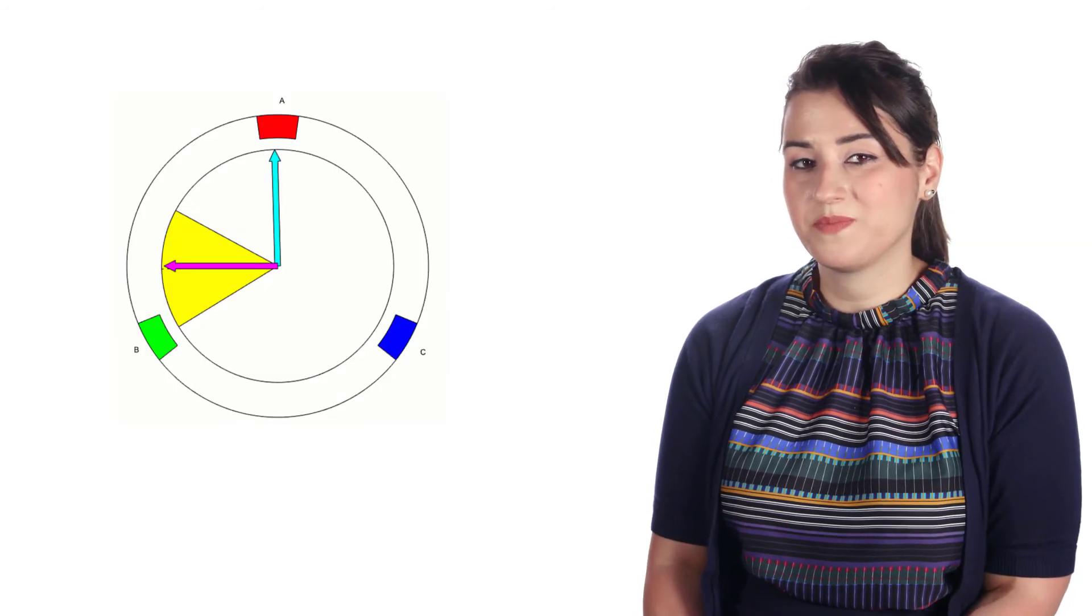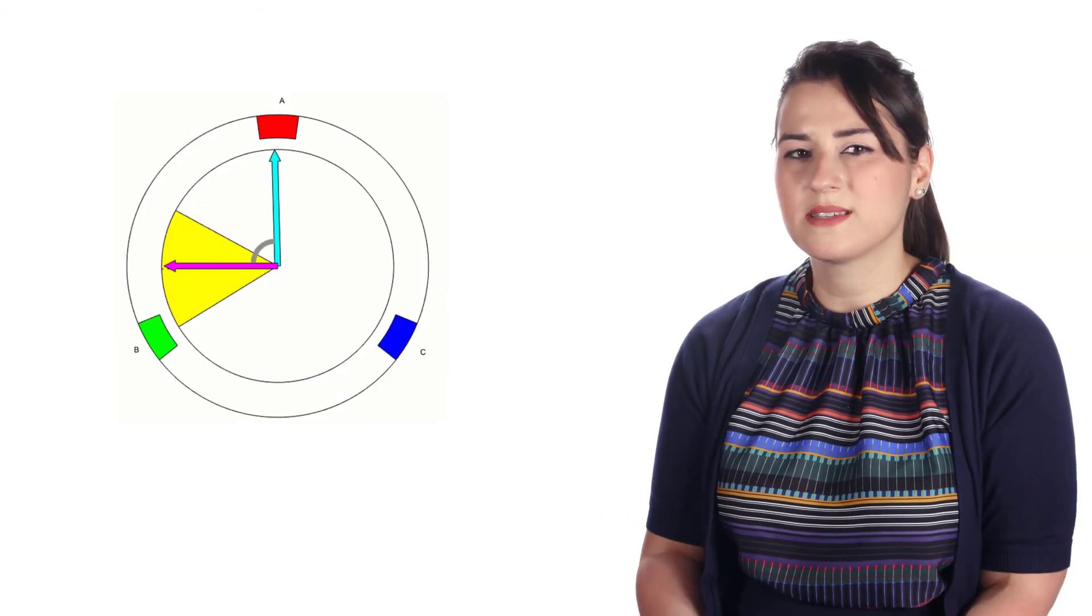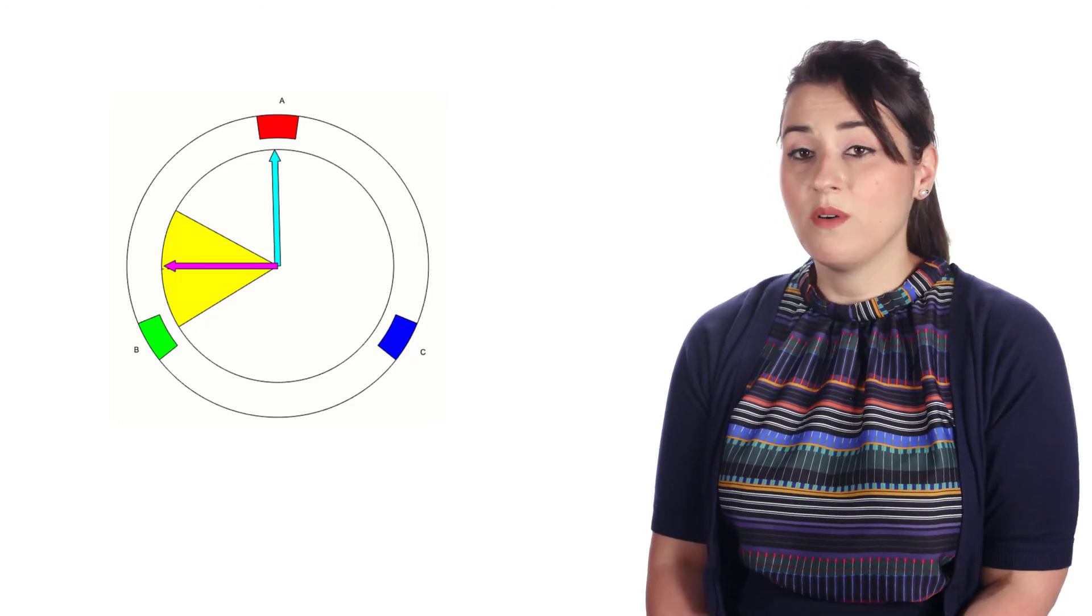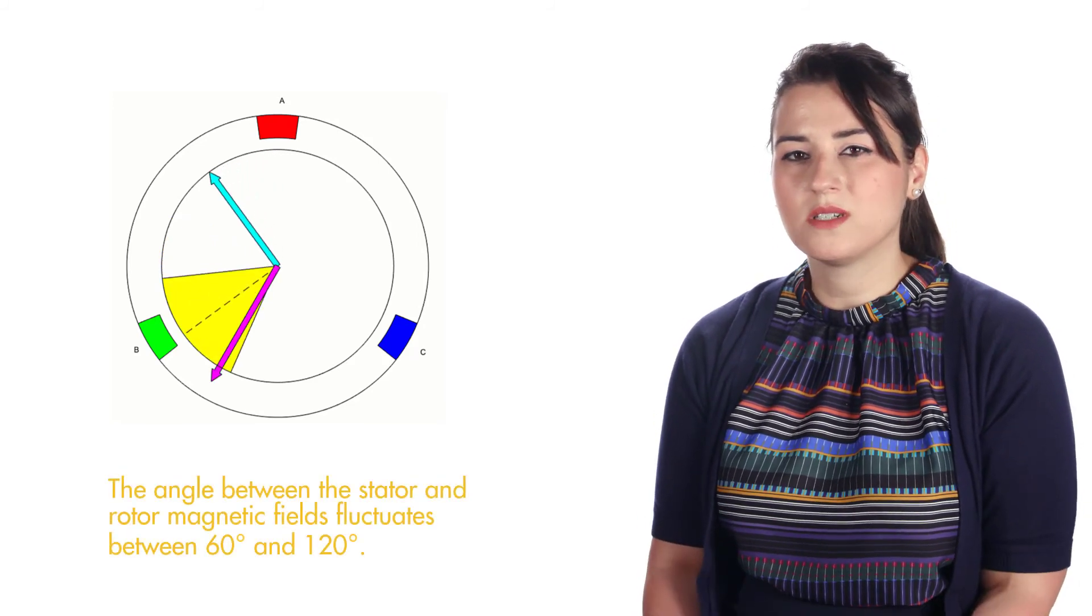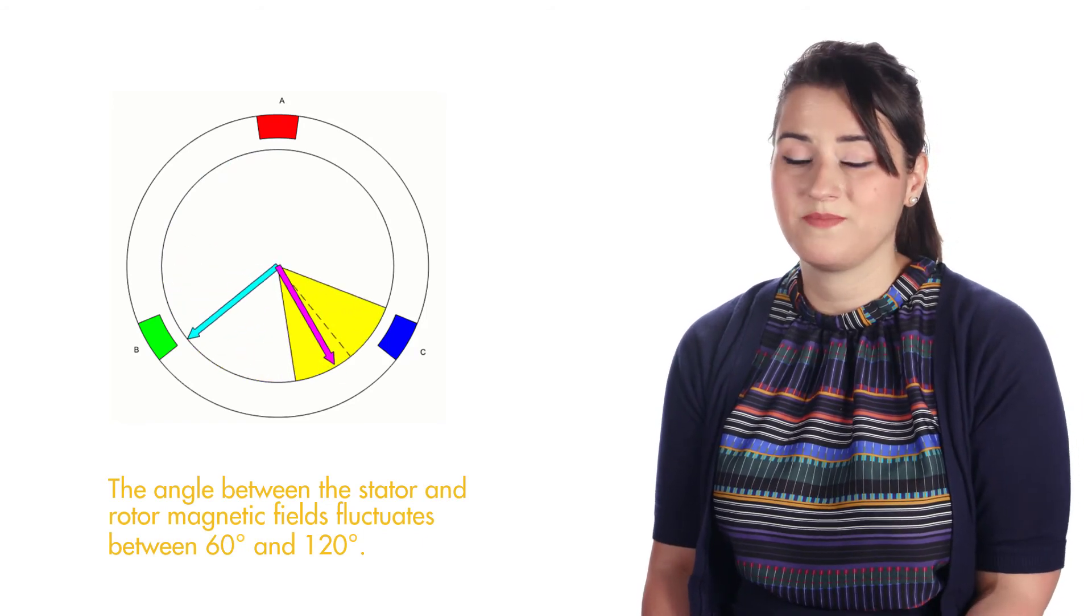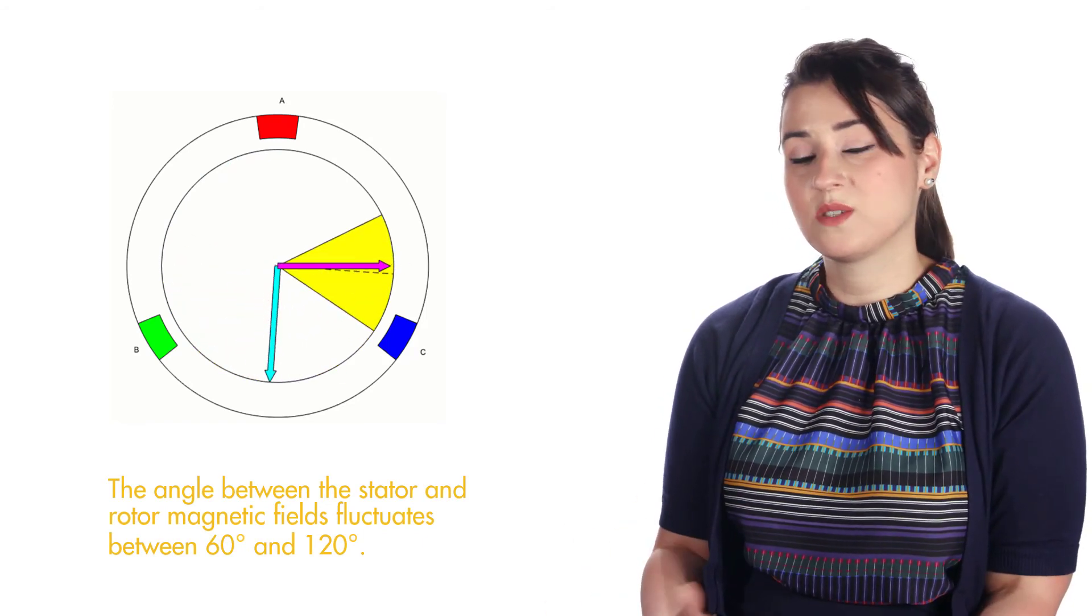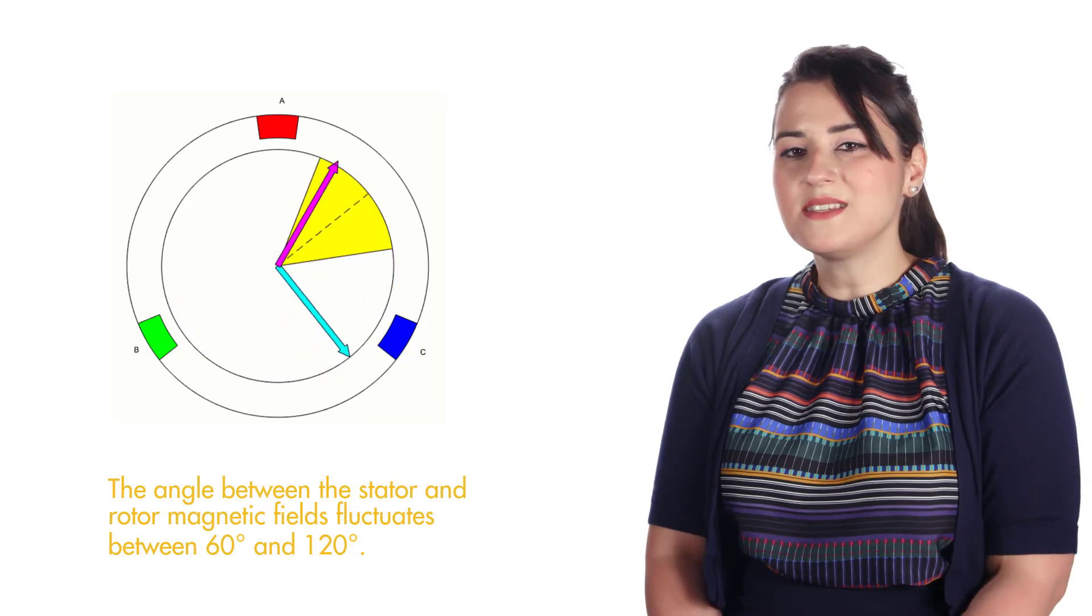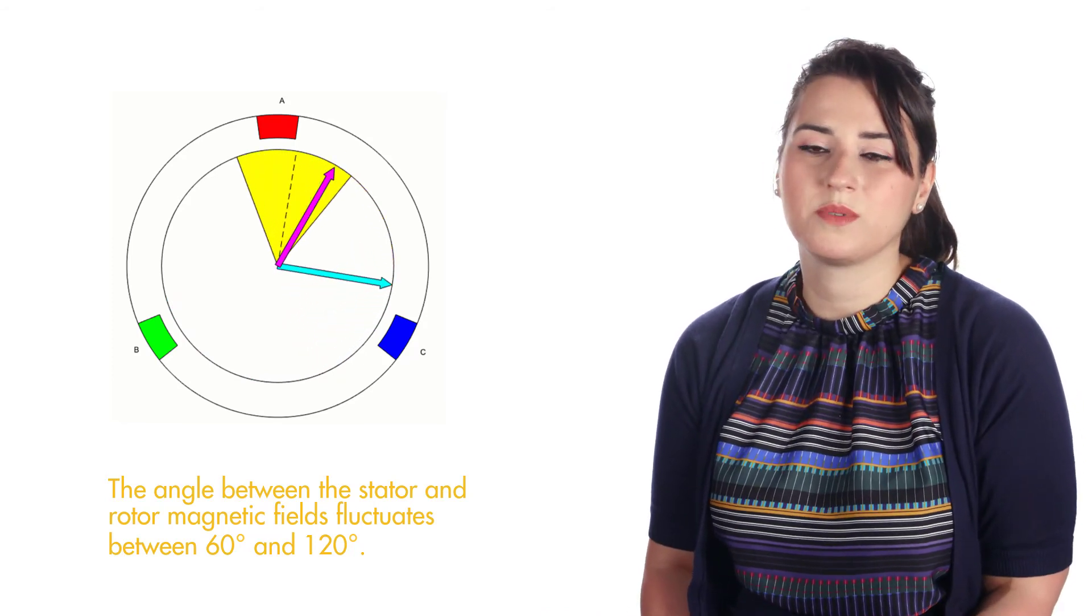Second, maximum torque occurs when the fields are at 90 degrees to each other, so the goal is to bring this angle close to 90 degrees. However, in BLDC motors, we never achieve 90 degrees with six-step commutation, but the angle fluctuates within some range, and this is due to the simple nature of the trapezoidal control.